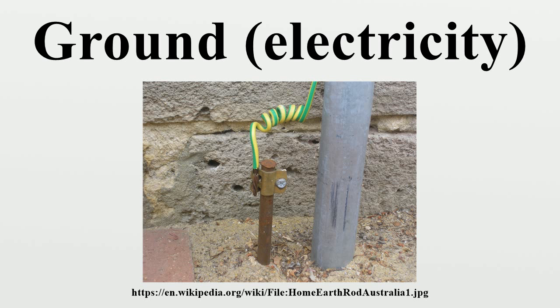to avoid accidents. Such functional grounds are normally wired in white or cream cable, and not green or yellow, separating low-signal ground from a noisy ground in television stations, recording studios, and other installations where signal quality is critical. A special signal ground, known as a technical ground, is often installed to prevent ground loops. This is basically the same thing as an AC power ground, but no general appliance ground wires are allowed any connection to it, as they may carry electrical interference.